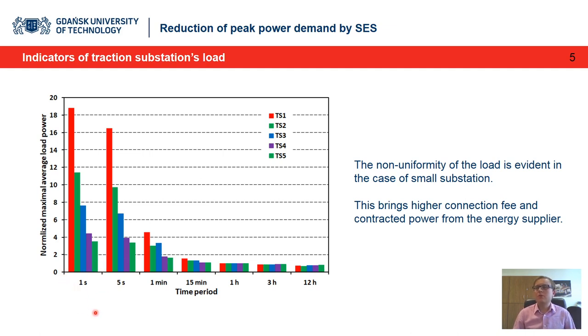Also, importantly, the supply cable and supply infrastructure from the public grid also need to be dimensioned for this bigger load value, which increases the cost of building the new substation, but can also increase operational costs, because most energy consumers pay not only for consumed energy but also for contracted 15 minute power, which depends on the 1 second power.